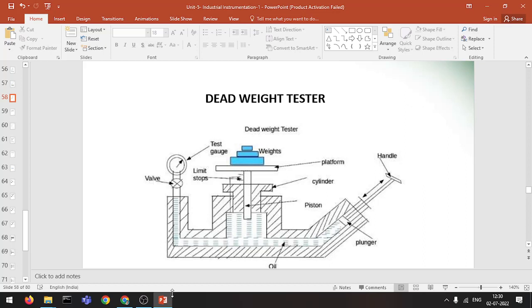So, dead weight tester is an instrument or a device which is used for the calibration of any pressure measuring instruments. The pressure measuring instruments can be electronic or mechanical. And this dead weight tester also is a piston cylinder type measuring device. Coming to the operation procedure, I'll explain along with the construction and the operation of this dead weight tester.